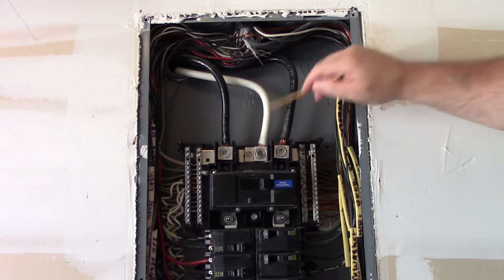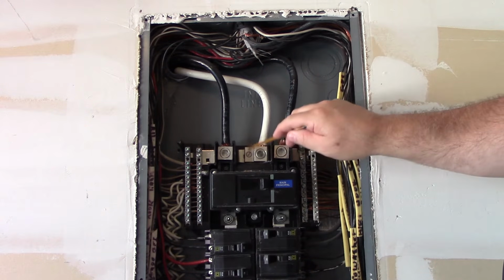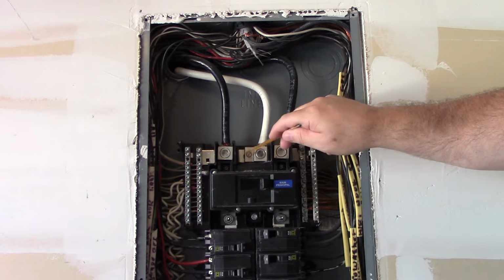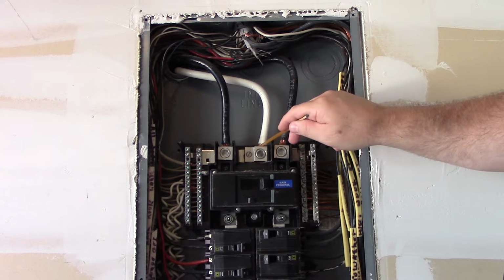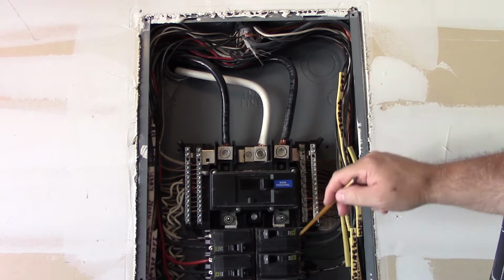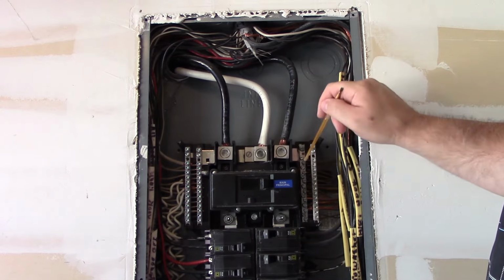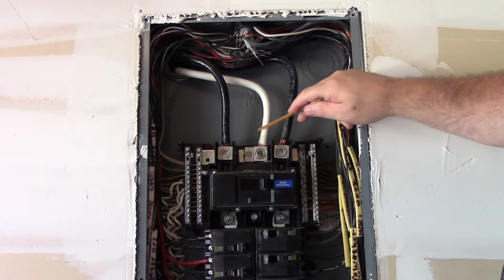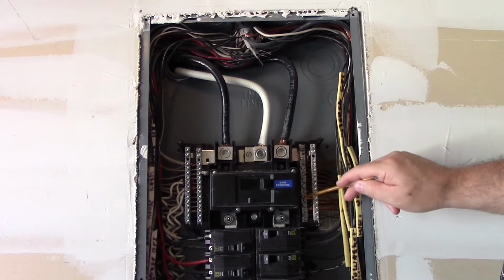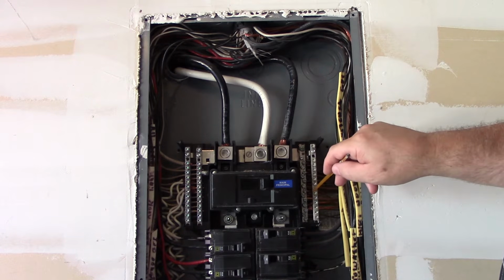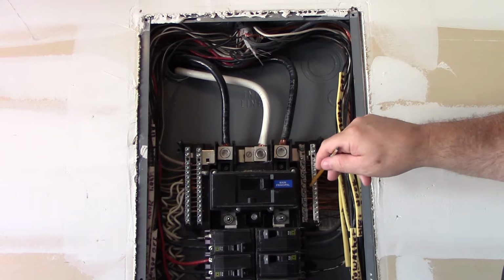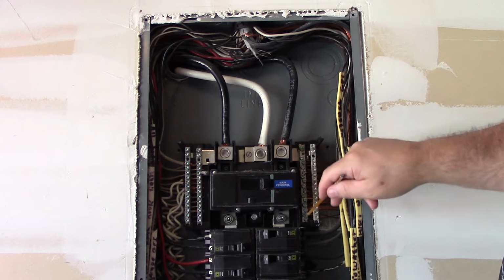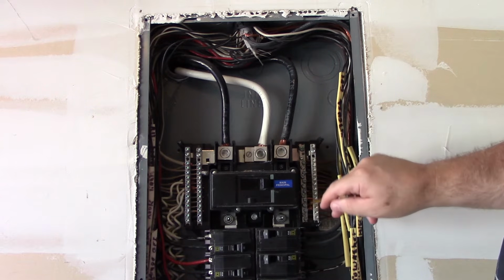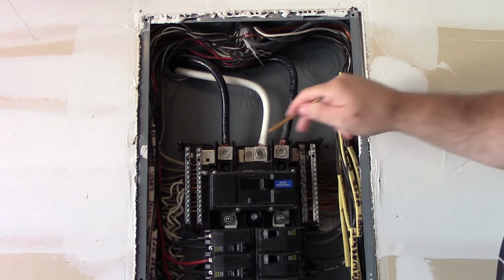All right, so that's what we got here. This lug right here is actually where they would bring the grounding electrode conductor to make that connection to the grounded conductor. But since this whole bus or this whole bar system is all considered one and it is connected to the grounded conductor, then as long as these lugs are sized large enough to take that 4-gauge copper in here or the 6-gauge copper, whatever it may be, then it's okay to terminate it here and not in here because it's all considered one.